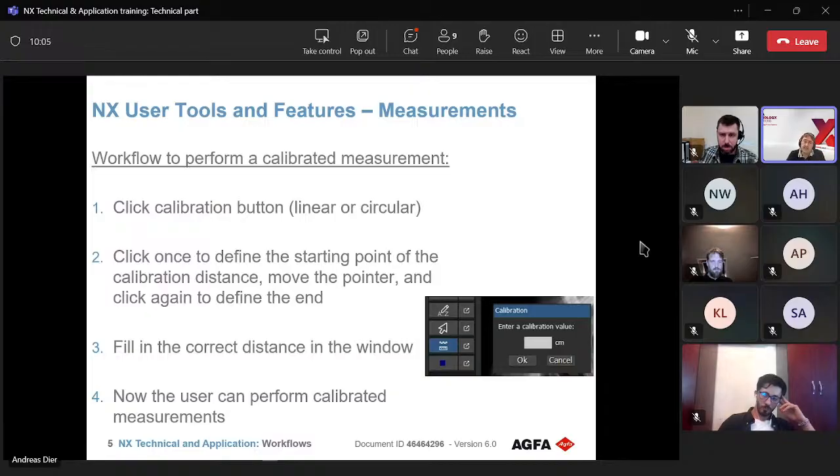It has to be in the range of the exposure so that we see it in the image, and it has to be at the same distance to the detector as the patient or the bone that we want to measure. So we may have to put it on some plastic or foam block which has the right height, so that it is in the right position.